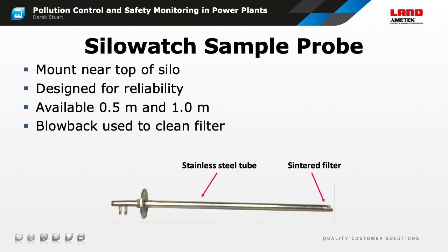Periodic blowback with compressed air keeps the filter clean for minimal maintenance. Any CO formed by spontaneous combustion will be detected in the headspace of the silo, so the sample point must be above the highest fill level, and it's important that the sample probe does not interfere with the loading chute. In most cases, convection ensures the gases in the headspace are well mixed.